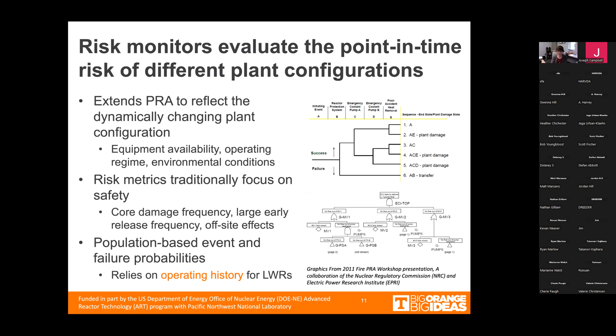So it may be that the pump has degraded a little bit, the valve is in a bad condition, and all of that's going to be lost to the risk monitor. And so the idea was trying to incorporate the real-time health of equipment into a risk monitor so that when we change the plant configuration, for instance, taking things offline to do maintenance, the risk monitor will reflect the condition of everything else in my actual plant operating in my actual conditions.